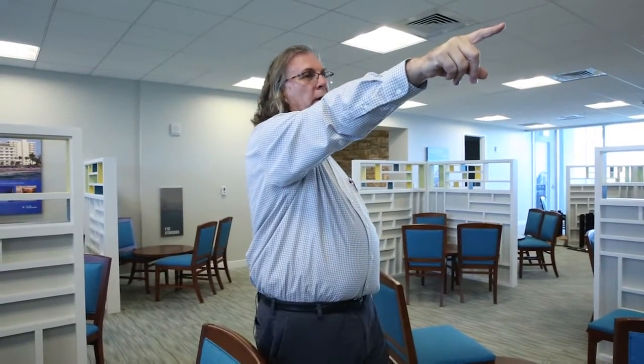So then you have the ultrasonic. So if you want these lights to turn on, both the infrared and the ultrasonic both have to detect you for the lights to come on. And this helps to alleviate false alarms, all right? The ultrasonic fills this whole room up, so somebody could be walking out of that office there, it's probably going to pick them up, all right? But we don't necessarily want that to trip.